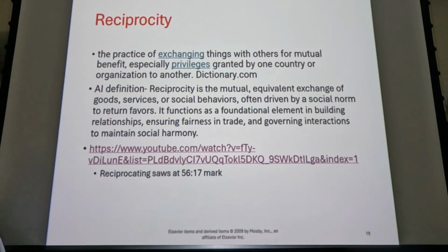So the point in the demonstration is just that. It's give and take, and give and take, and give and take. That's all the law of reciprocity is. And what that means is mass equals mass. It doesn't really matter how you arrive at the mass. The exposure to the image receptor, as long as your machine is shooting properly, 50 mAs equals 50 mAs. It doesn't matter what mA station you set and what time you set, you should get 50 mAs as long as your machine is shooting properly within a certain degree of accuracy.